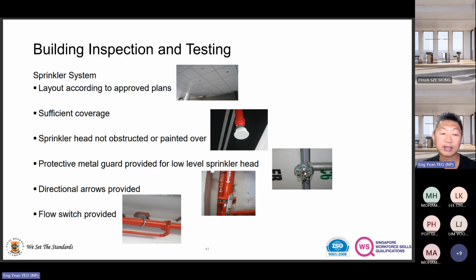Then there's the protecting guard. Usually once you can raise your hand and reach it - like for example at 2 meters or 2 meters plus and 3 meters - you should have this guard installed. During your walkabout or inspection, if you check and see a sprinkler head that is too low with no protection, you can take photos to recommend that a protective metal guard should be installed.